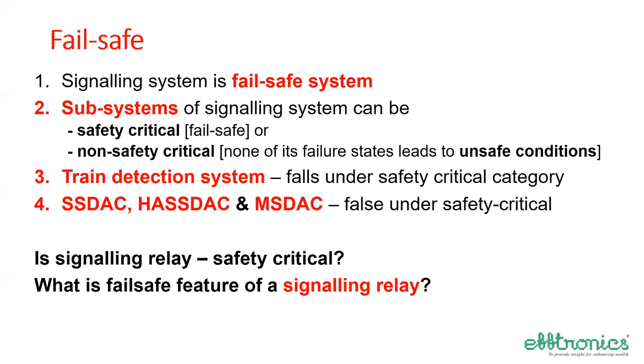When somebody asks us, what is the fail safe feature of a signaling relay? Normally, it is this feature which will not allow both front and back contacts to close at the same time. That means when any one of the front contacts is closed, none of its back contacts shall close, and vice versa. That is the feature which makes it fail safe.